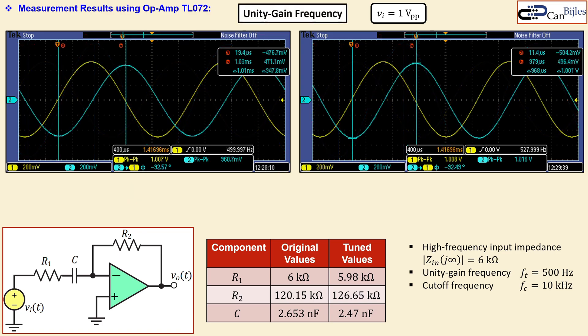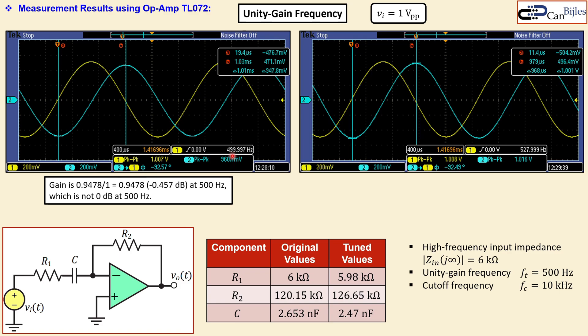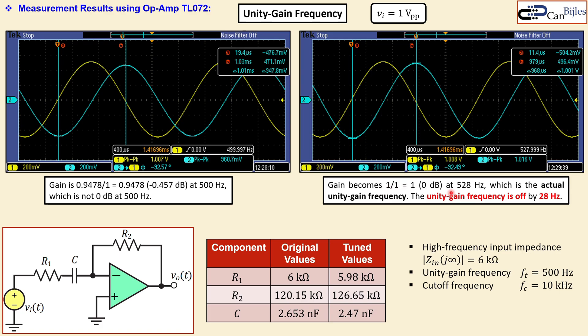For the unity gain frequency measurement, at 500 Hz the output is approximately 948 mV peak-to-peak (input is 1 V peak-to-peak), so 0 dB is not yet reached. The frequency at which 0 dB is actually achieved is 528 Hz, giving an error of 28 Hz compared to the 500 Hz specification.